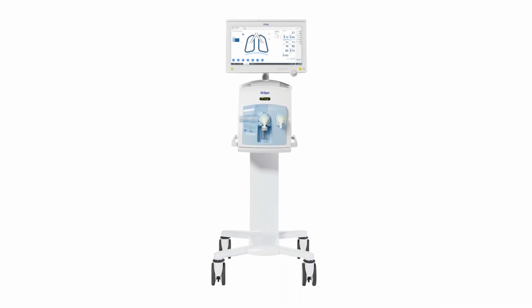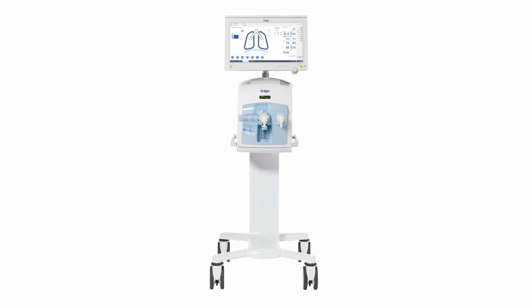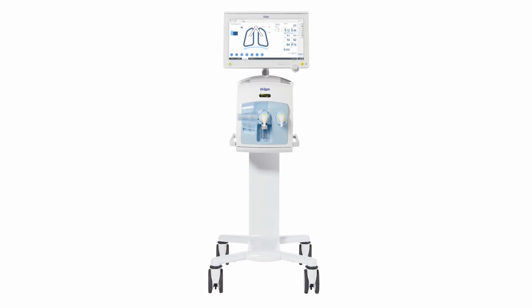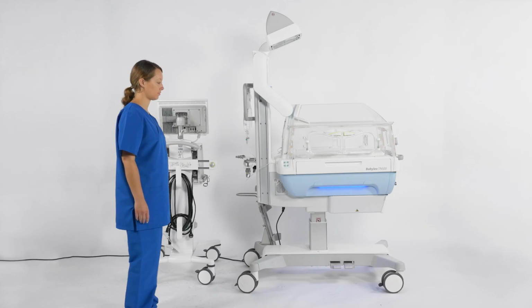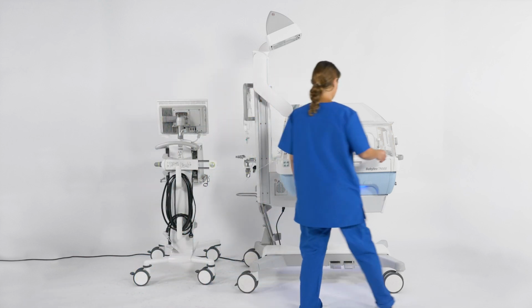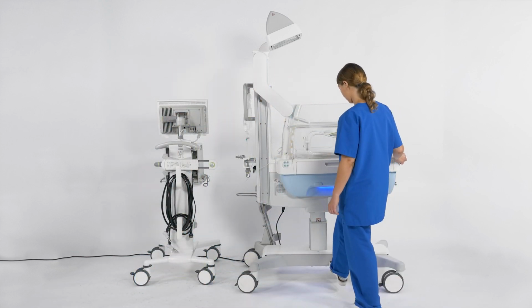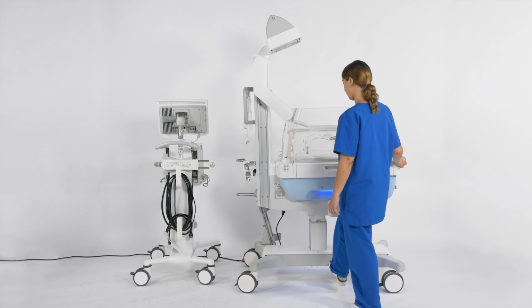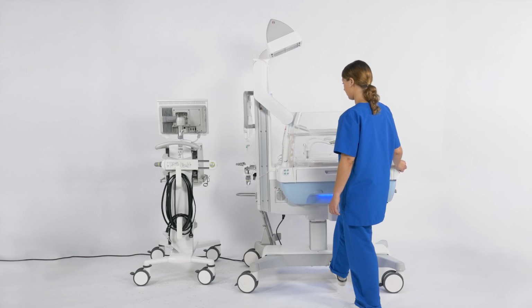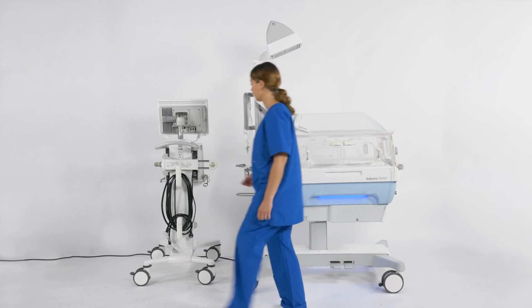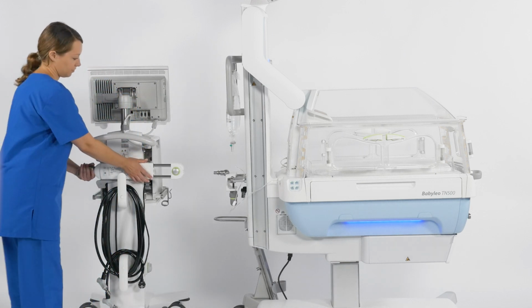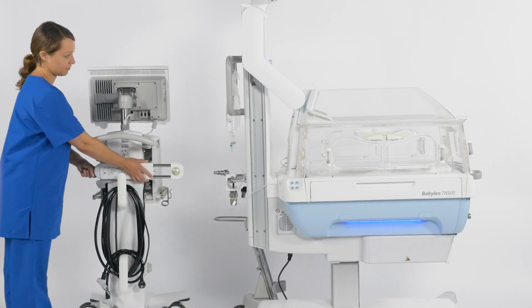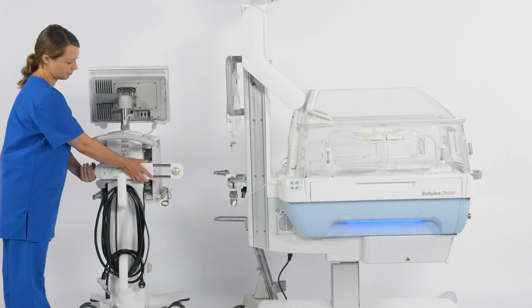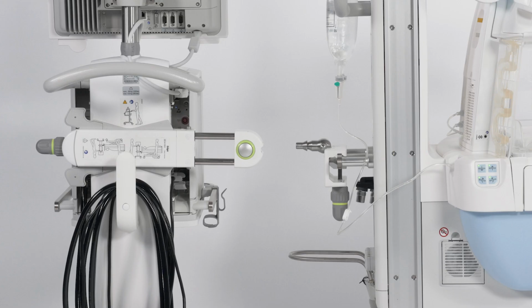As an additional feature, the Babylog ventilator can be connected to Babyleo for even easier patient transport. First, ensure Babyleo is set to the correct height so the bedside coupling for mounting is visible. Babylog can be mounted on the standard rail either on the column side or the front side. Second, attach the device side coupling to the Babylog trolley. Check the position of the mounted bedside coupling to ensure both parts are positioned at the same height.